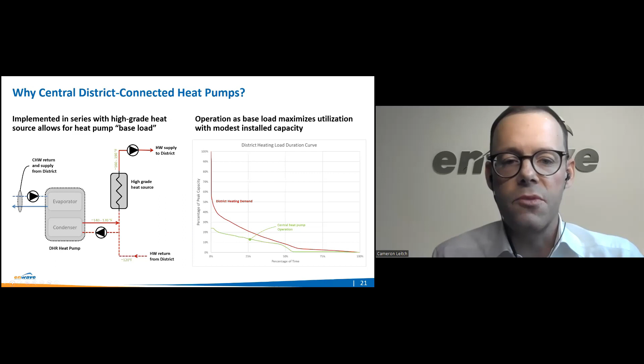The graph on the right shows a representative load duration curve for a district heating water system, with demand shown on the red curve and the operation of a district connected heat pump in green. The area under the green curve represents the utilization of the heat pump, and the difference between the red curve and the green curve represents the higher grade heat source energy. In this example, the heat pump makes up somewhere around 25% of the installed heating capacity, but more than 60% of the annual heating production, which has a significant impact on carbon emissions relative to business as usual.